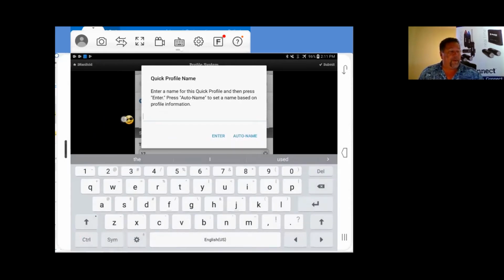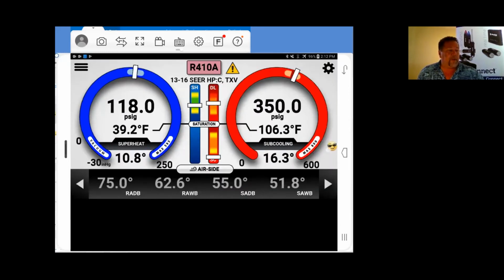We've gone through this before on the profiling training. I can either name it myself or I can use auto name. I'm going to be using this on several different units, so I'm going to use auto name. And as you can see right up here on the top, 13 to 16 SEER, heat pump, in cooling mode, TXV. And as you can see, when we got all started up, we've got everything going. Here's our pressure targets, our superheat and our subcooling. This is actually what we have here. 10.8 and then 16.3. Obviously, we're out of range over here on our subcooling.